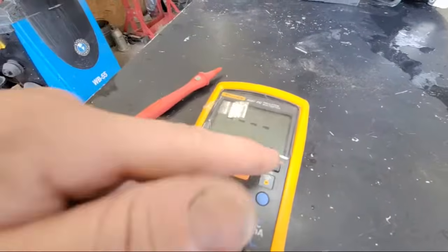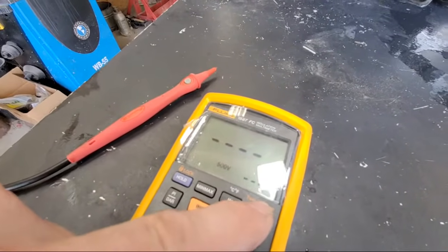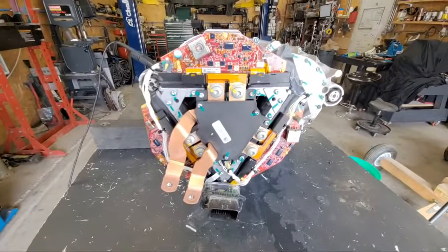Basically this meter, if you see it says 500 volts right there, that means my test voltage—watch, I could do a test voltage of 1,000 volts. Be careful, Maddie. 50 volts, 100 volts, 250, 500, or 1,000. Since this is a 400 volt system, we're going to do a test voltage of 500.